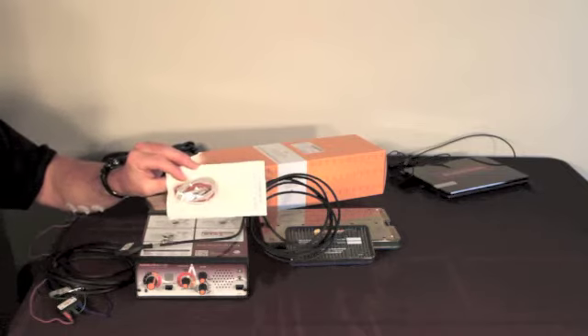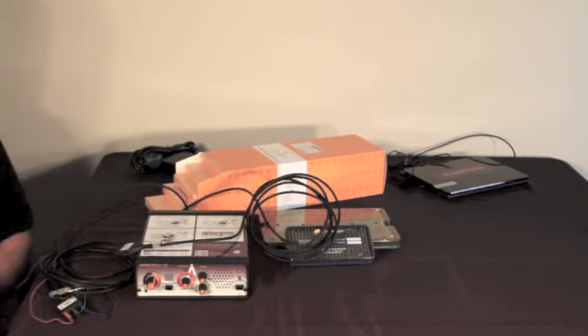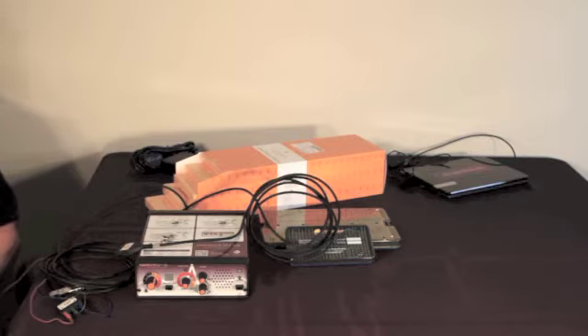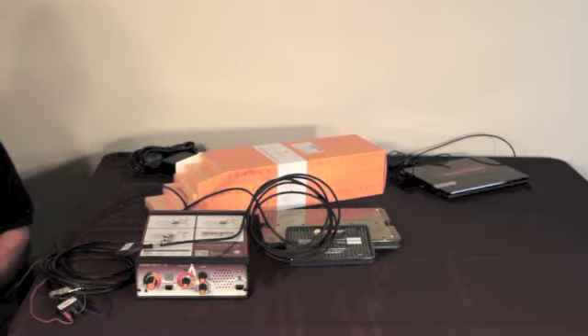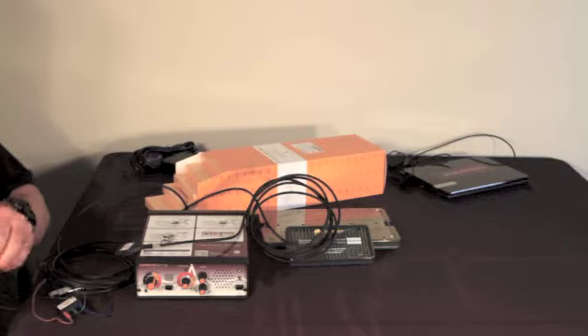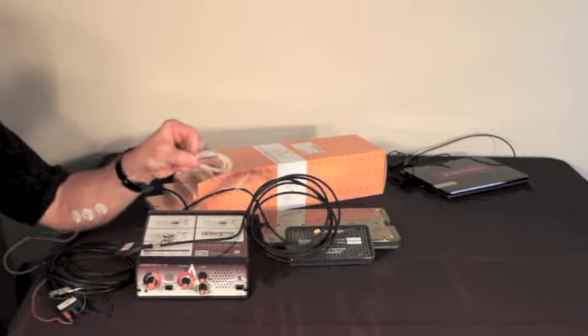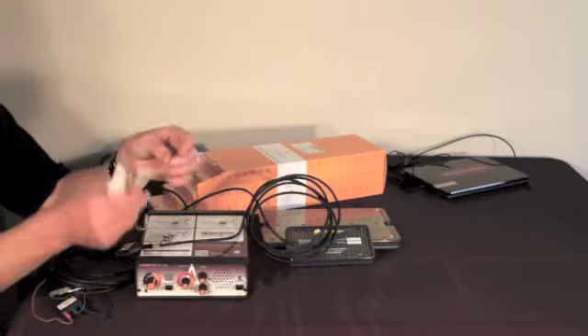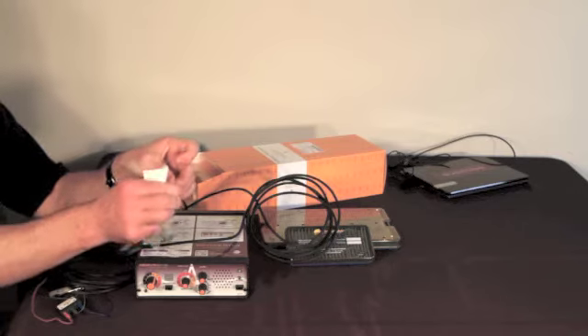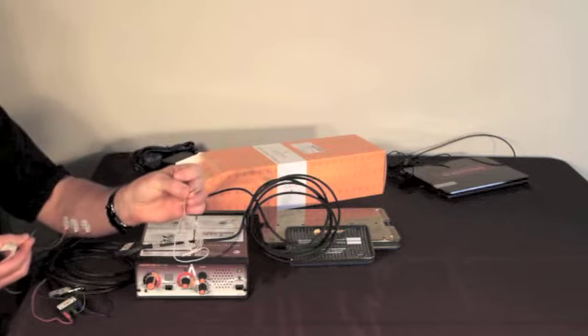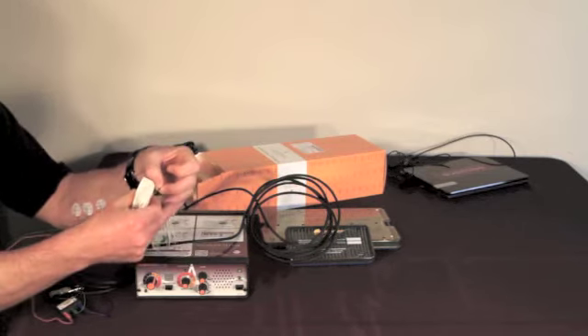Inside there's a red and a white wire. The white wire is a needle electrode that is the return for the stimulation applied by the probe. Direct the circulating nurse or the doctor to apply this needle subdermally in the shoulder, as shown in the illustrations.